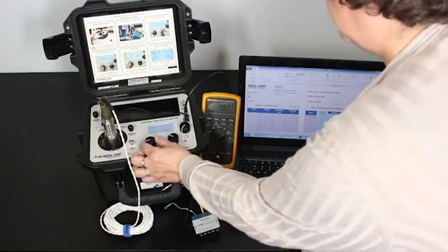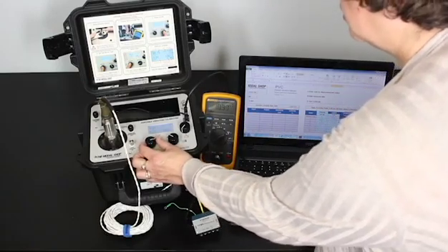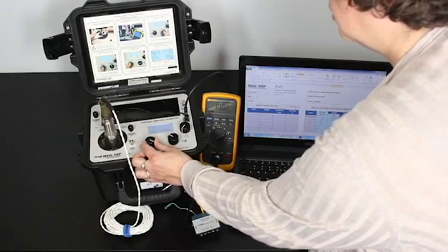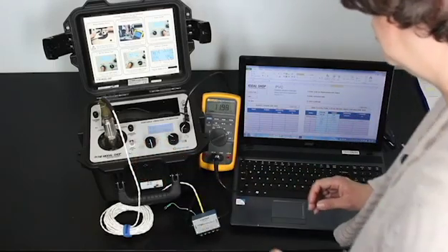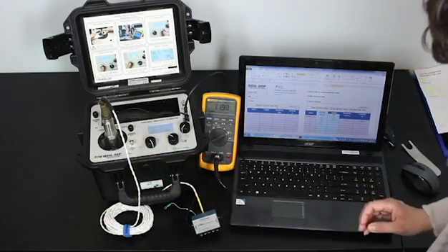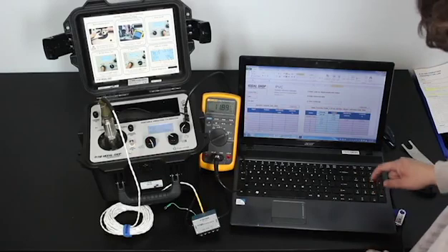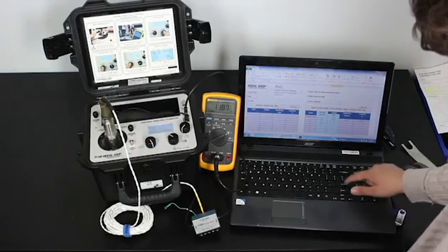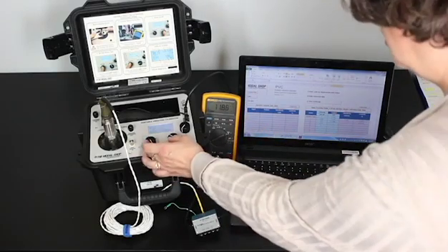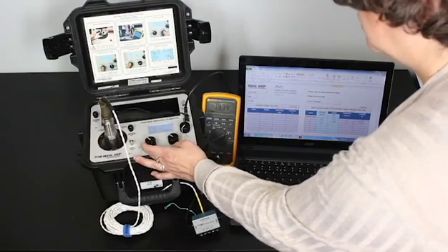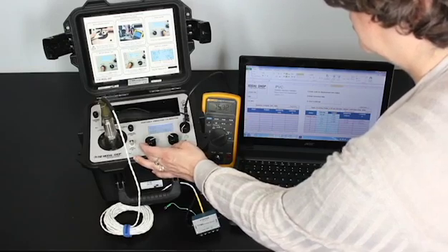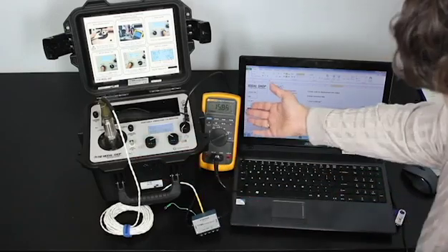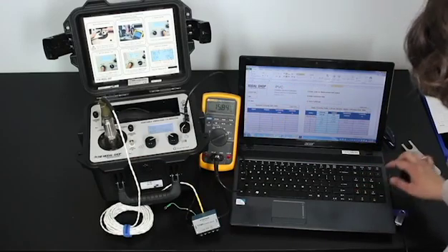Our next test point is 0.5 inches per second peak. And now our output is 11.89 milliamps. Now to 0.75. And we read 15.85 milliamps.